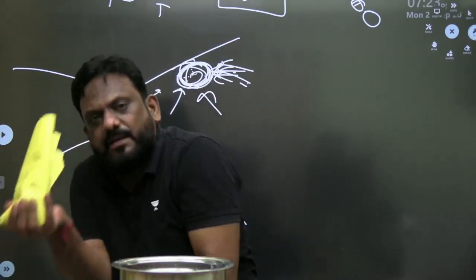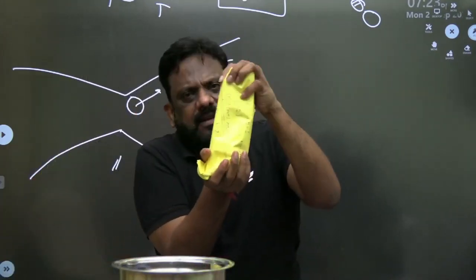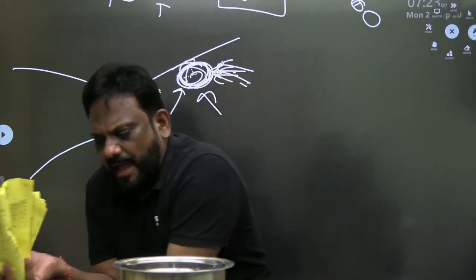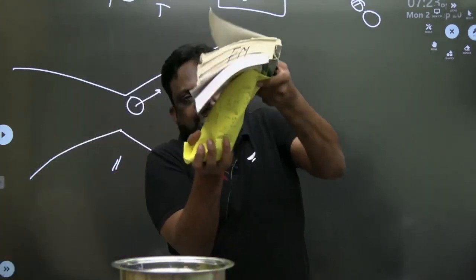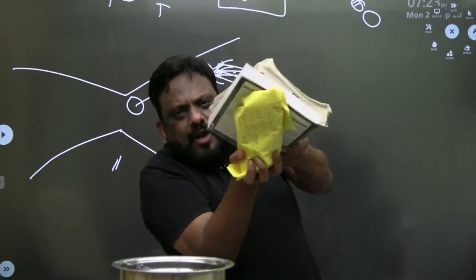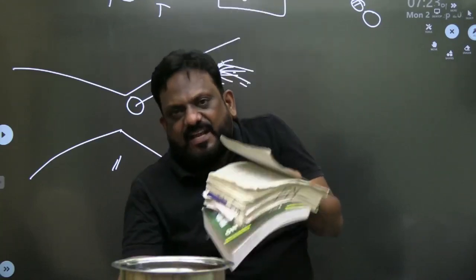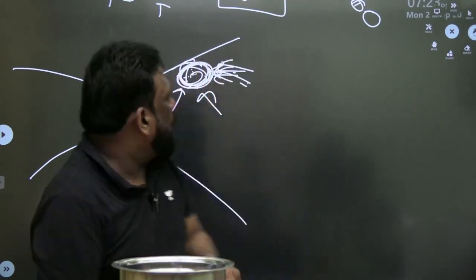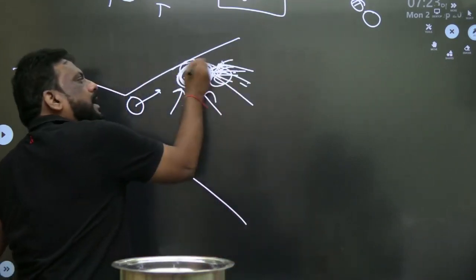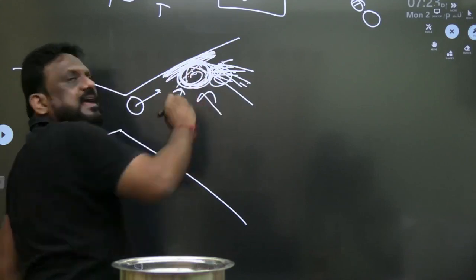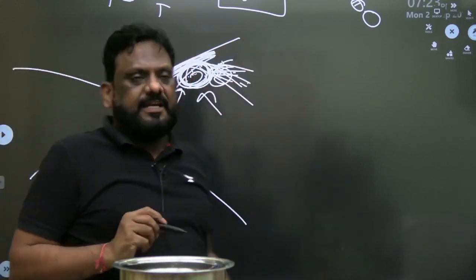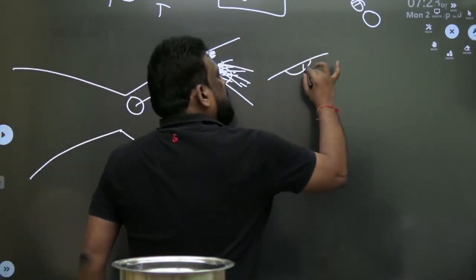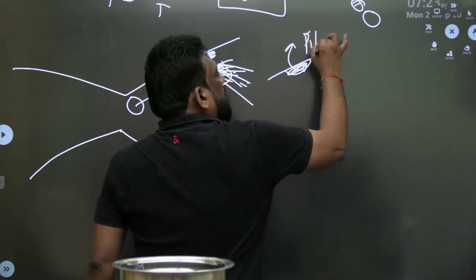Look. Now let us assume this to be a bubble. Let us assume this to be a vapor bubble. And look, high pressure, and this will completely collapse. After it completely collapses, all the weight will come onto the surface, the metallic surface. When the weight has fallen down completely, what will happen now? When this weight, this pressure, severe pressures are created, even shock waves are generated, and thereby the metal is eroded, which we call pitting.